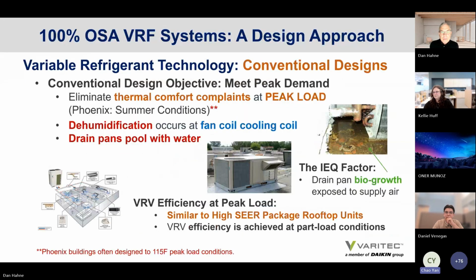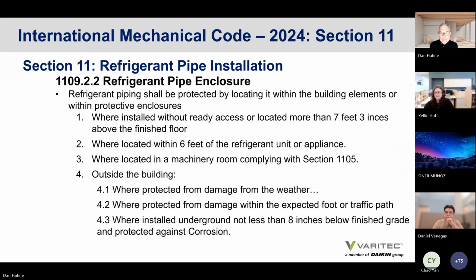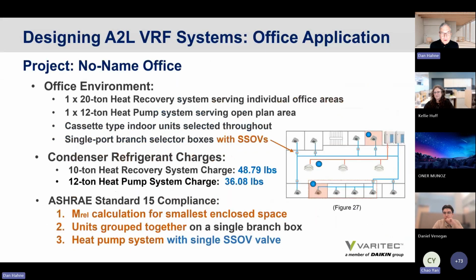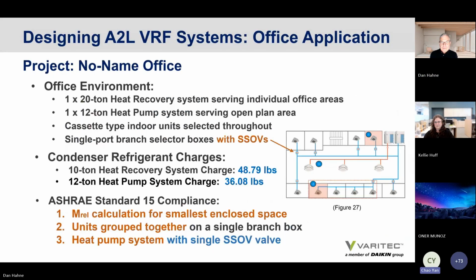Hey, this is Xiao here, Dan. Can we go back to the office design example where we have a group of offices? Yep. Okay, here we go. So in that example right there, we have 4 indoor units served by 1 safety shut-off valve, right? Yes, that's a heat pump zone for that large open area, correct? And we're taking the releasable charge amount for the combination of the 4 indoor units.